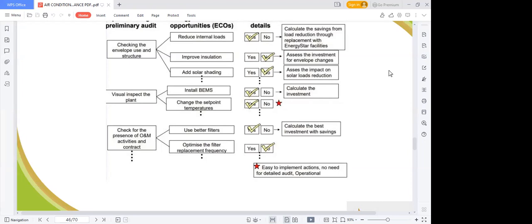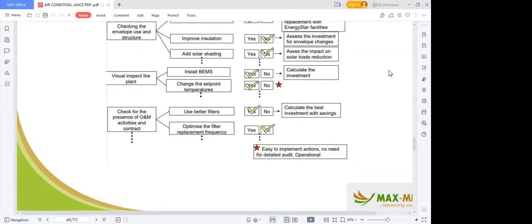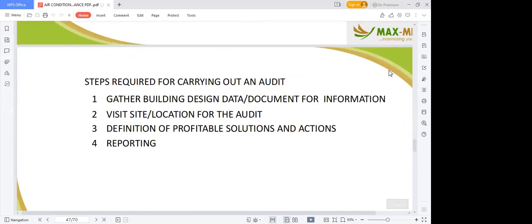Know where the unit was installed, know the name of the manufacturer, get the model of the equipment, check if the equipment has a maintenance record, call in a company or an experienced person to do the condition assessment of the equipment before they take them over, then do a detailed report and submit it to your owner. The steps required for carrying out an audit: gathering building design data and documents for information, visit the site location for the audit, definition of profitability, solution and action, then reporting. All this is a summary of what I have just explained to you.